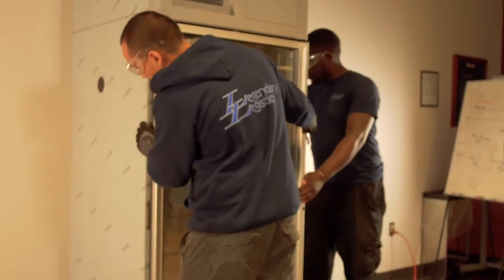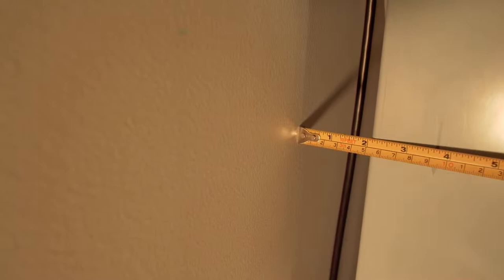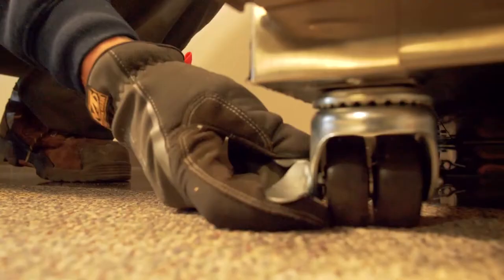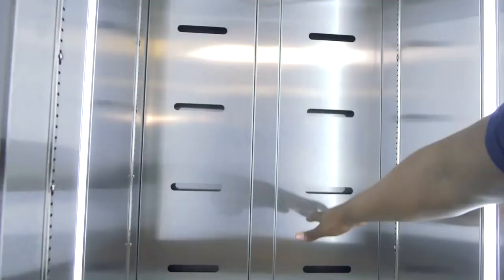You should hear the compressor begin to work if power is confirmed. For final positioning of the refrigerator, the ventilation clearance required is 2 inches from the back and 10 inches from the top. Once in position, lock the front two casters.